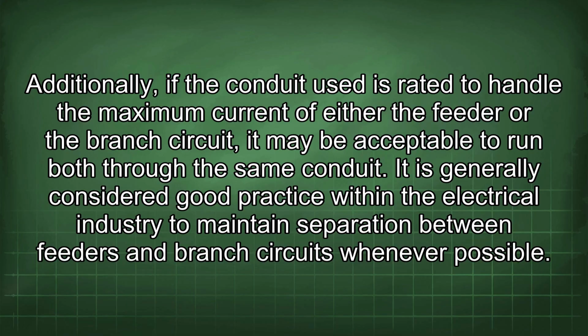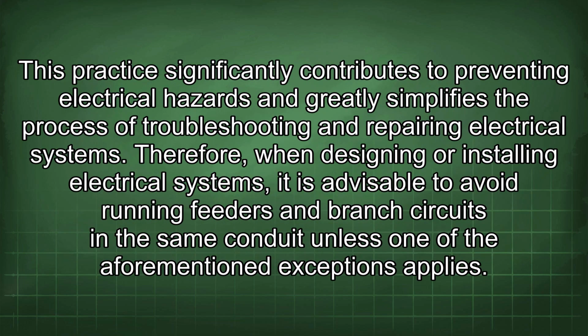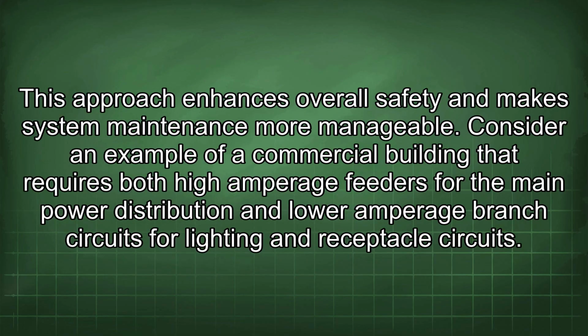It is generally considered good practice within the electrical industry to maintain separation between feeders and branch circuits whenever possible. This practice significantly contributes to preventing electrical hazards and greatly simplifies the process of troubleshooting and repairing electrical systems. Therefore, when designing or installing electrical systems, it is advisable to avoid running feeders and branch circuits in the same conduit unless one of the aforementioned exceptions applies. This approach enhances overall safety and makes system maintenance more manageable.